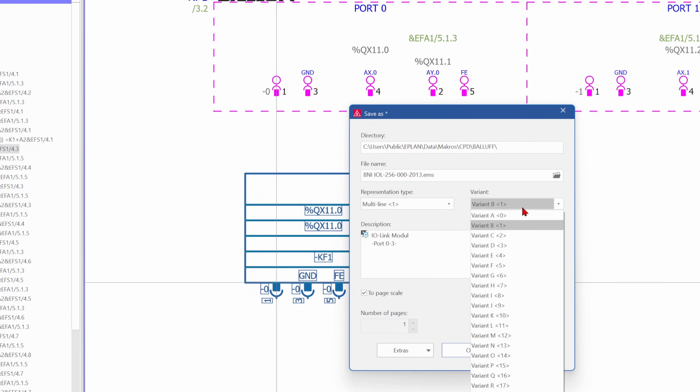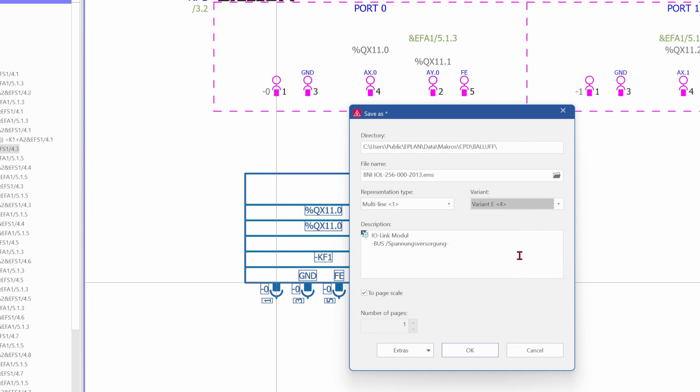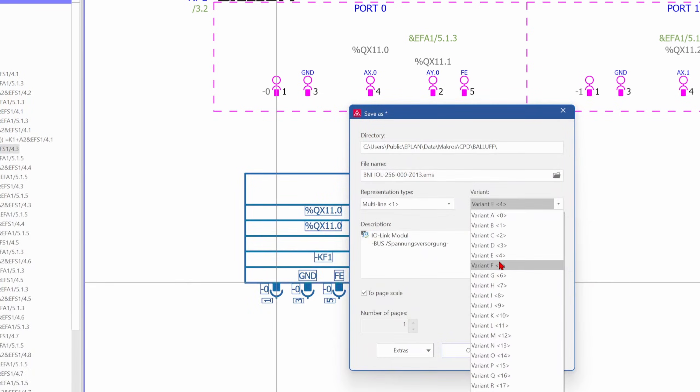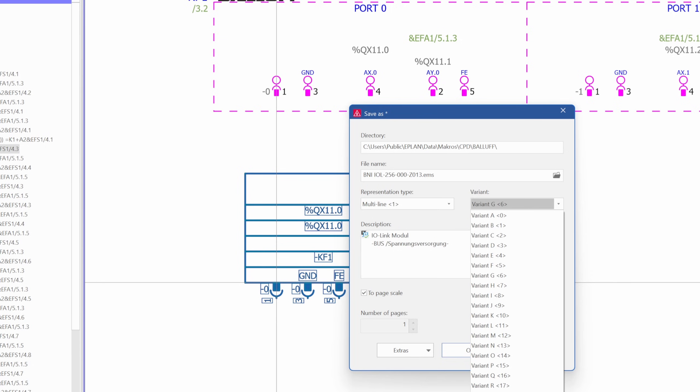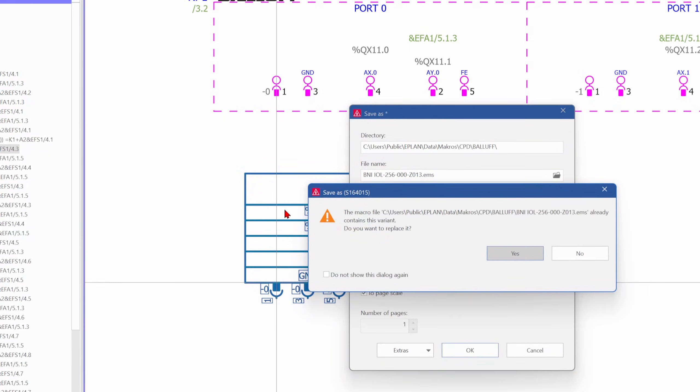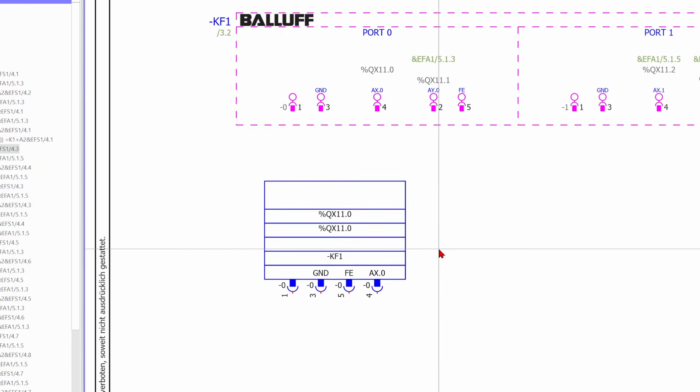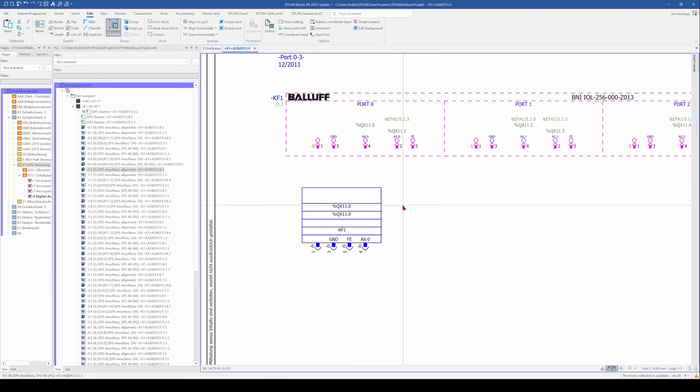Now for sure you need to select your macro here from this device, you need to check where it is and you need to have the presentation type to multiline. This is normally automatically set in EPLAN when you create a macro from the multiline page. The problem now is that you have maybe already some variants of the macro available. You see variant A, variant B, variant C is port 4 to 7, variant D is the power supply and variant E maybe is free. If you are not sure, you need to insert it one time or you need to check the master data. I use variant Z and make a description that this is the IO connection.